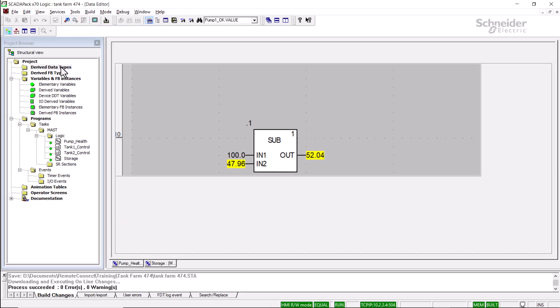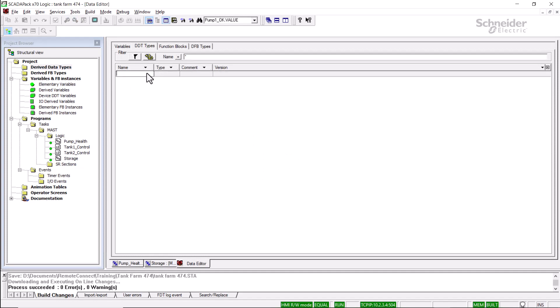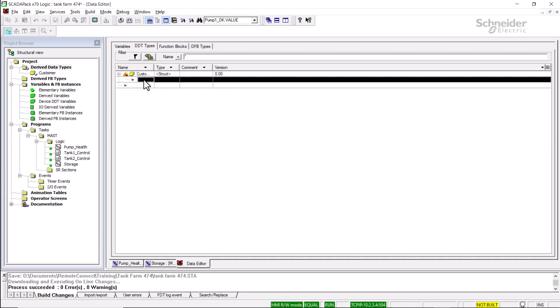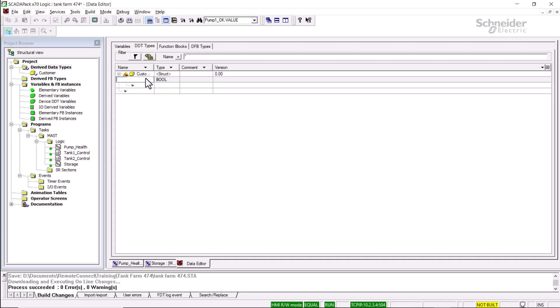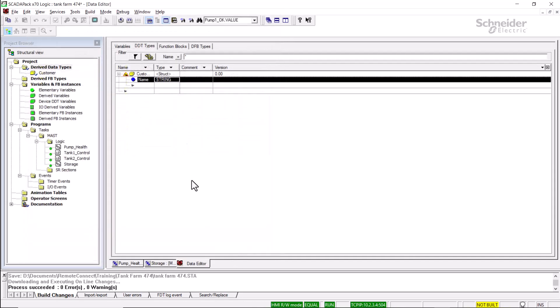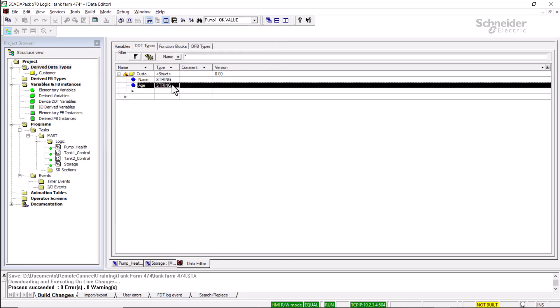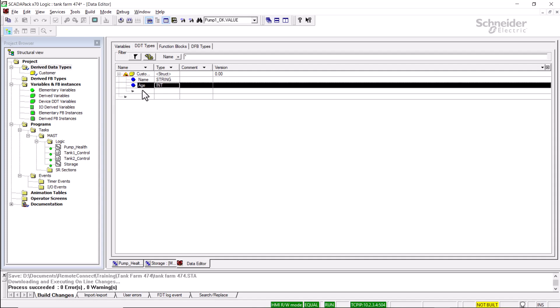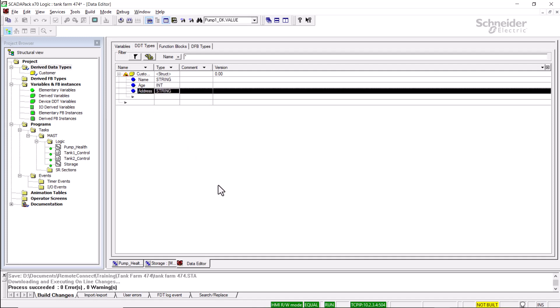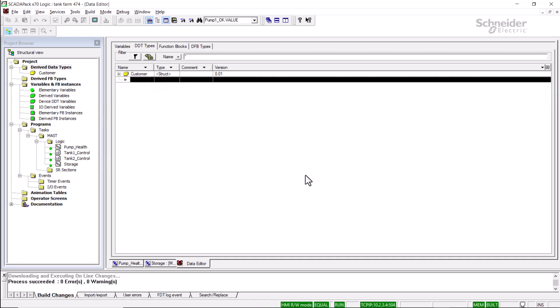I'll open the derived data types folder and create a new derived data type. I'll name this structure Customer. Yes, we confirm the modification. Now I'll add a few variables into this structure. First I'll create a variable within the structure called name. We'll assign this a data type of string. Then I'll add one called age and we will make this an integer. And we could add a third one. We could call this one address and we'll create this one as a string again. Now that I've got that done, I'll build changes. Control-B. I can now use this derived data type in further online edits.